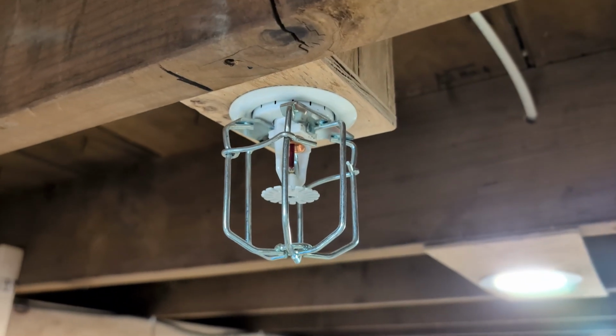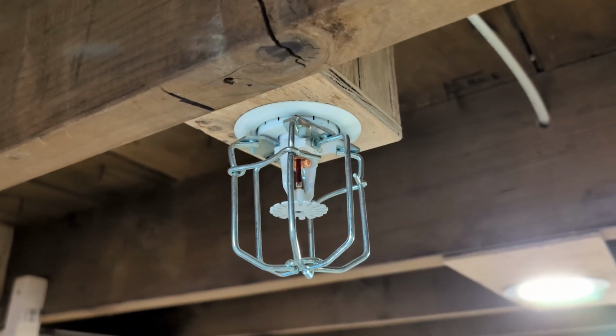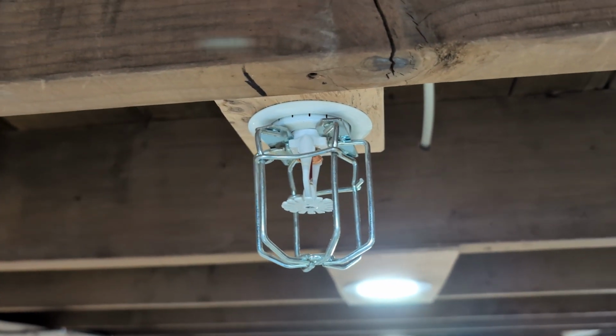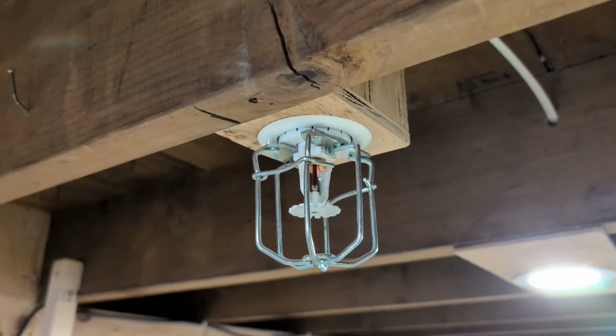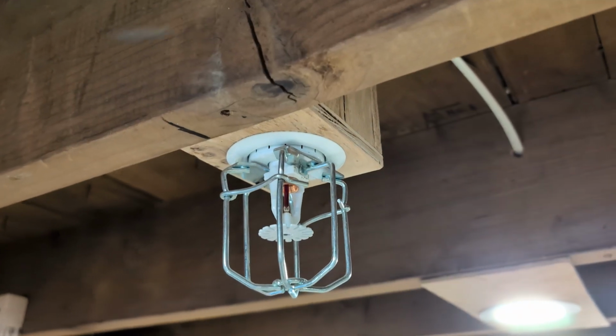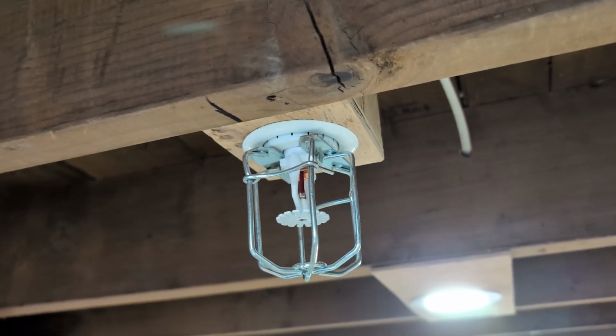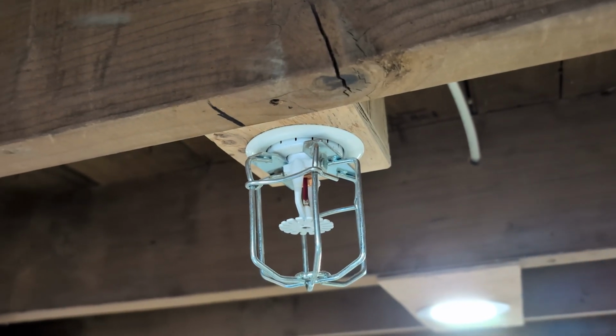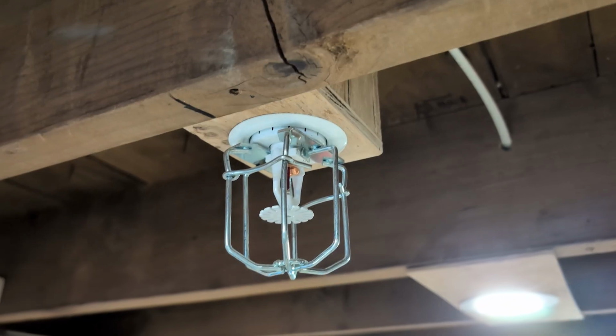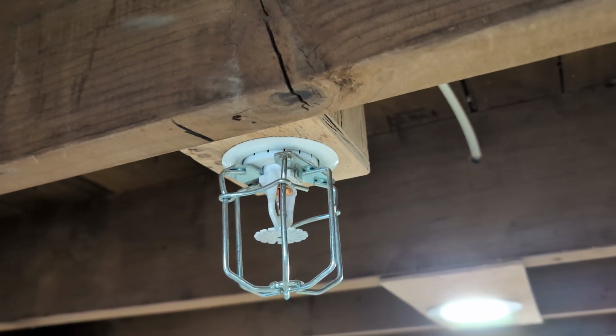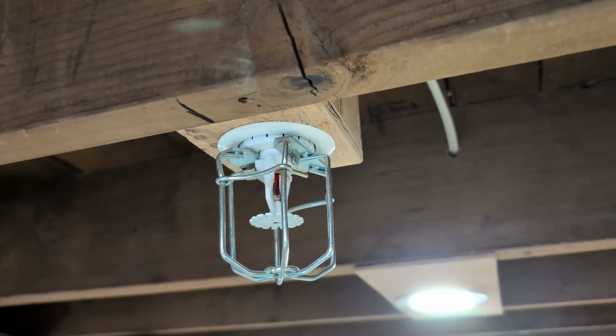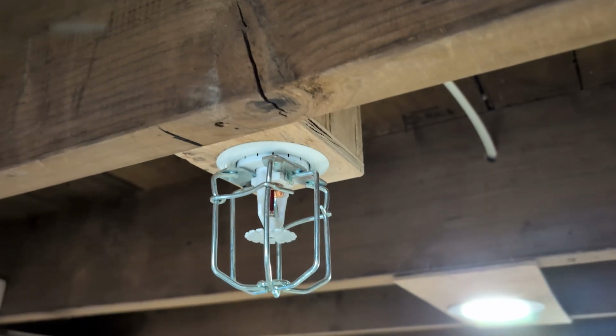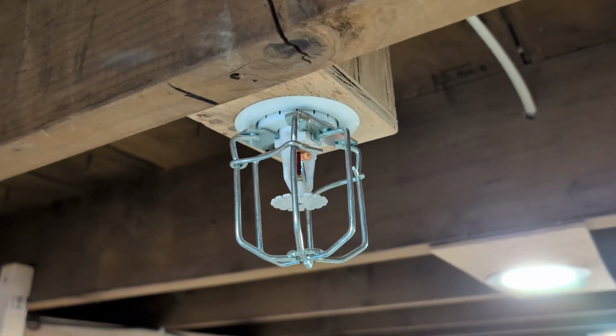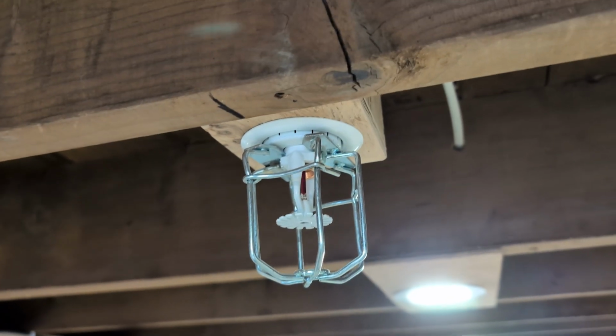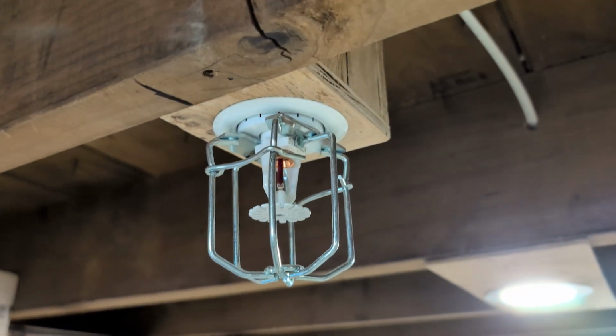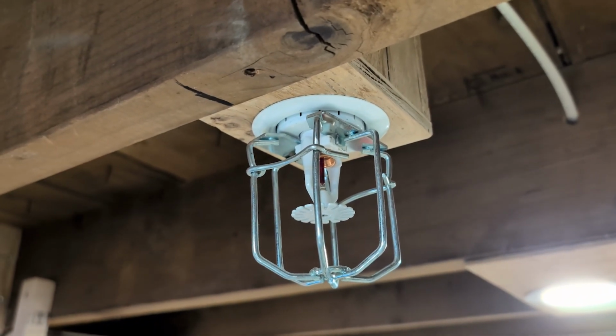Another question I get is, how do we put sprinklers in unfinished basements? NFPA 13D simply says that if the sprinkler piping itself doesn't require there to be a ceiling for the protection of the sprinkler piping, and for the most part the sprinkler piping that we're going to be using for these types of systems is either going to be listed to be exposed or you can use a metallic piping, we don't need to be putting a ceiling in. So you just anticipate that there is a ceiling, and that's how you calculate your spacing. And then if someone ever comes in and finishes a basement like this, the sprinklers are already in the proper location.